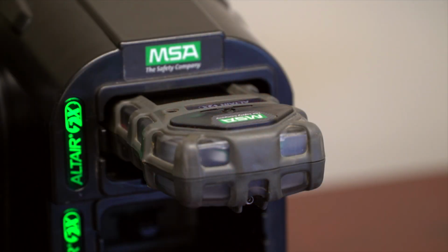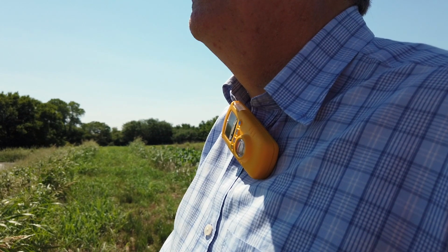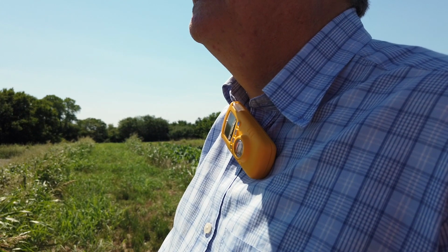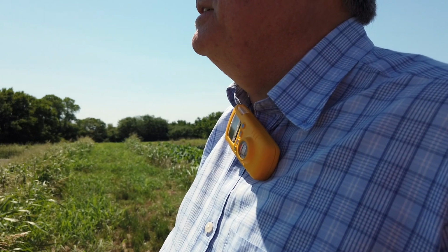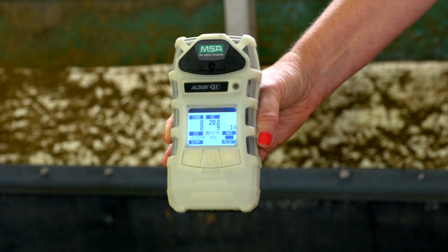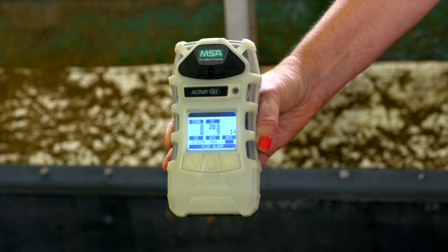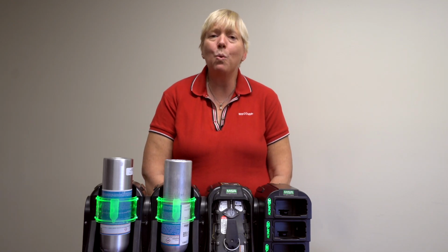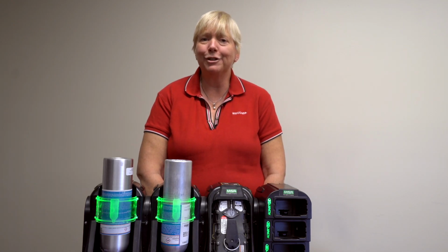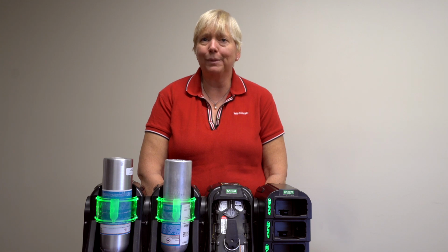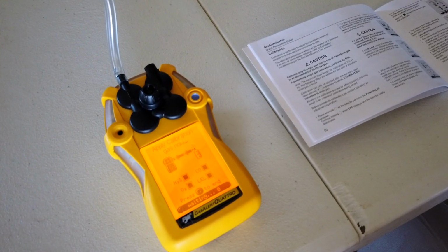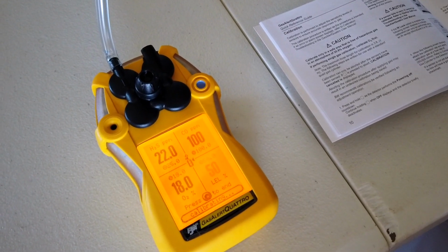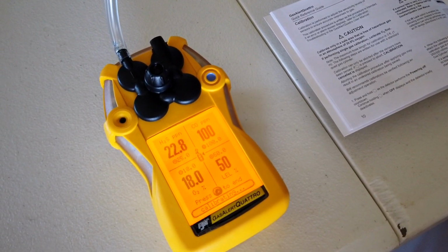Whether it uses a charging station, such as this monitor, or it has an internal battery, such as a single gas monitor that goes for 2 years, being sure that you have enough power is important. There are 2 key tests that you want to perform on your gas monitor to be sure that it is functioning properly. The first one is called calibration. Calibration checks the accuracy of the sensors within your monitor.